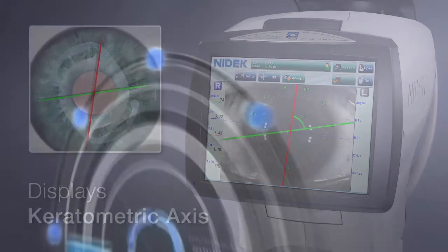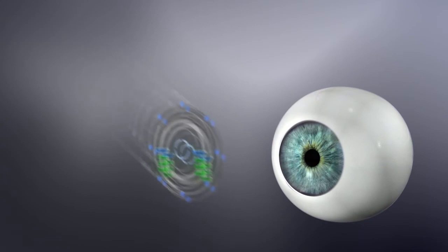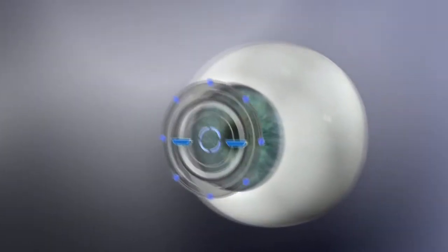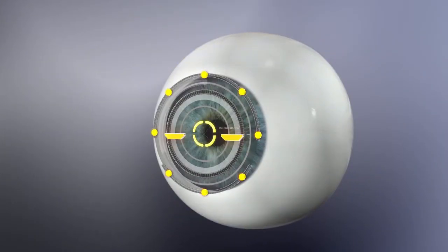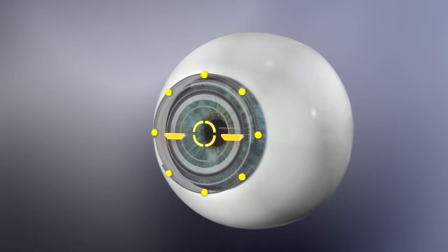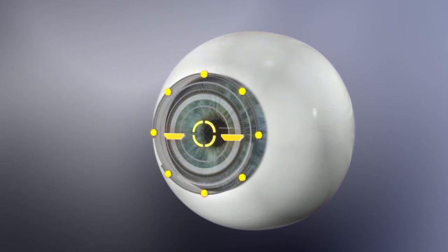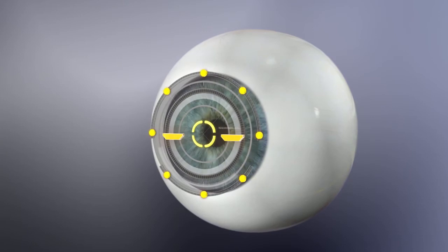The speed of the AL scan is made possible by 3D auto-tracking, which follows patient movements on the X, Y, and Z axis. As soon as the auto-tracker obtains correct alignment, the auto-shot function immediately begins capturing patient data.